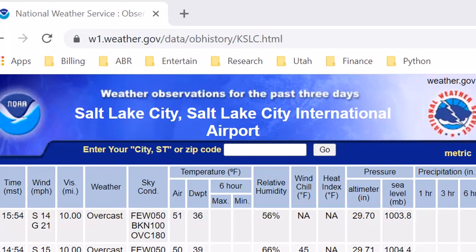The short answer is no. Because if we take a closer look, this 100.38 kilopascal was in fact measured at sea level, as indicated in here, which is very different than the actual pressure in our LINAC vault, which is 85.6 kilopascal in our last example from our monthly data, measured at a much higher altitude where our LINAC vault is.